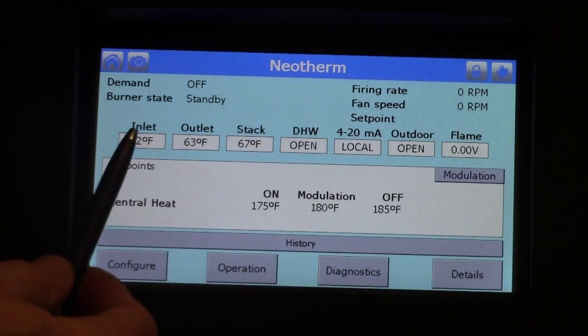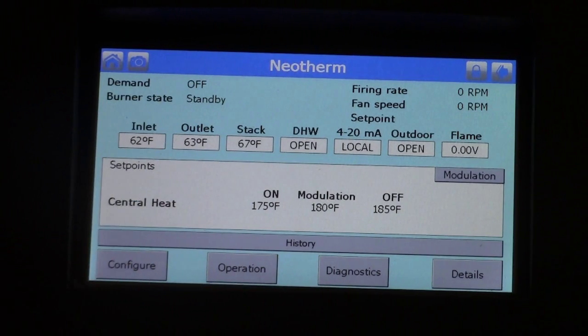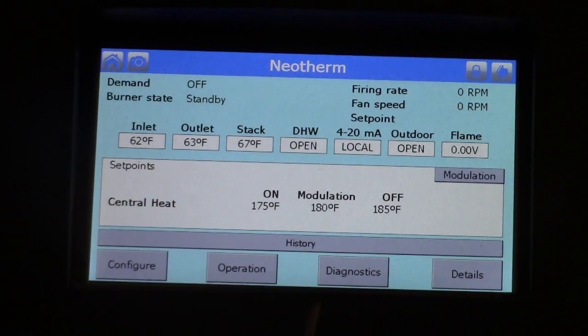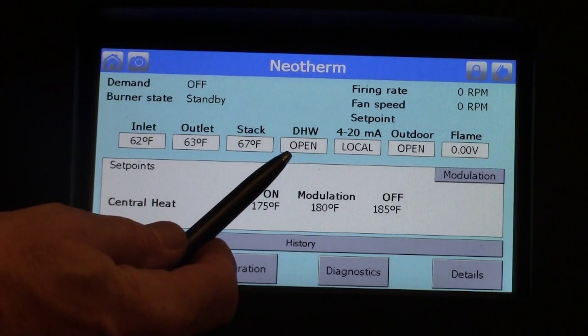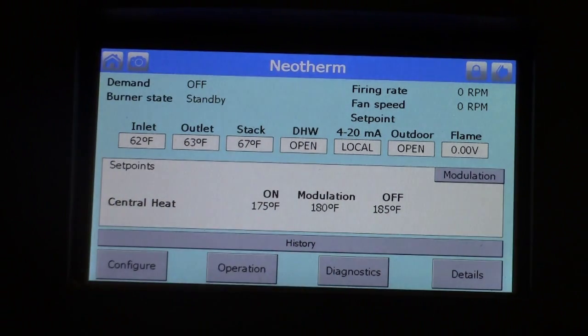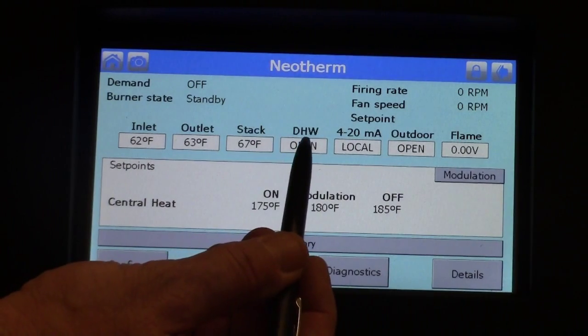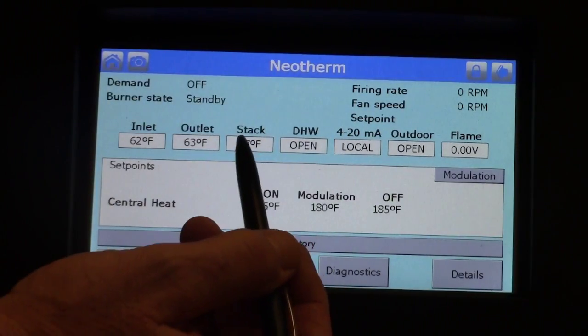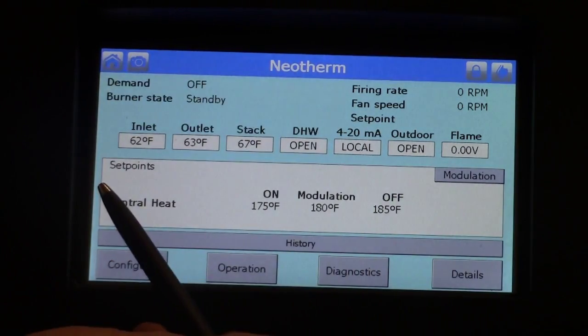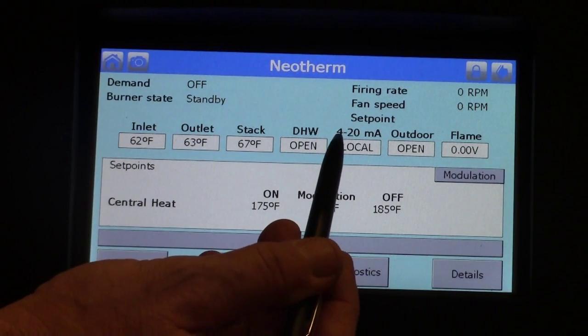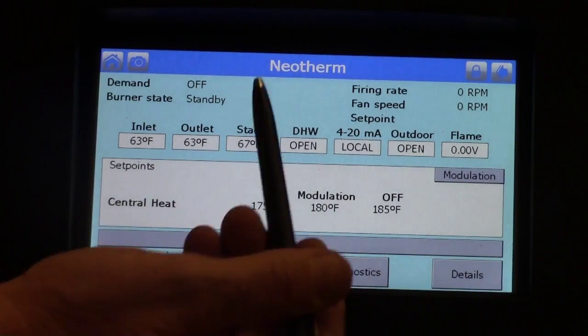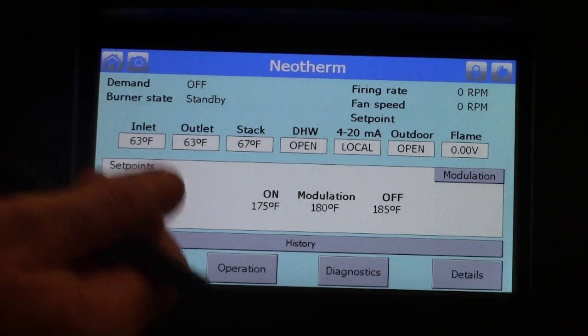Down here we have the inlet temperature. There is an inlet sensor and an outlet sensor inside the boiler, so you can read the inlet temperature, the outlet temperature, the stack temperature (which is our flue temperature), and domestic hot water call. If we're doing domestic hot water off an indirect, it would either read the temperature if you're using a sensor, or if you're using a mechanical aquastat, it would read 'closed' or 'shorted,' meaning we're calling for domestic hot water. We can also control 4 to 20 mA — if your application requires it and you're giving it a 4 to 20 mA signal, it would display the signal internally. Right now we're set up for local, a standalone application without 4 to 20 mA running.